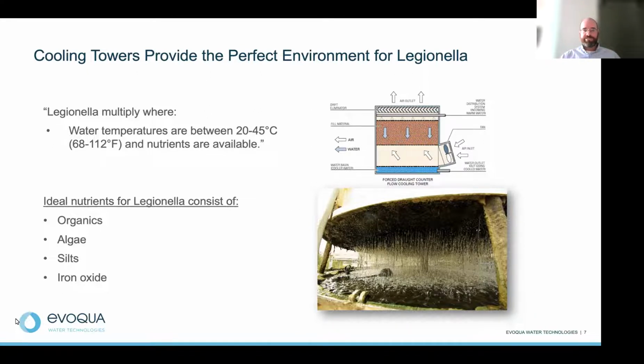But why is bacteria such a big deal for cooling towers? Well, it's got the perfect environment. Cooling towers have warmer water. Typically, the water temperature is in the sweet spot for bacteria to grow. As we mentioned before, it's a big air scrubber, so it's sucking in all those nutrients. It's got a lot of nutrients to feed it. Lastly, it's also sucking in silt, sand, and debris. And that creates a nice protective habitat where those biocides can't get in and penetrate, allowing that biofilm to grow and proliferate. So it's got that perfect environment for bacteria growth, including the bad L word, Legionella.